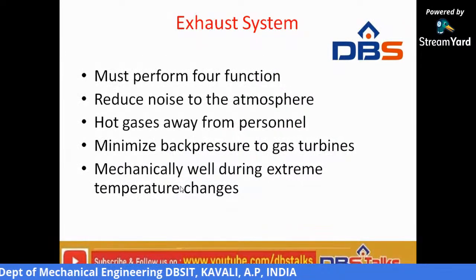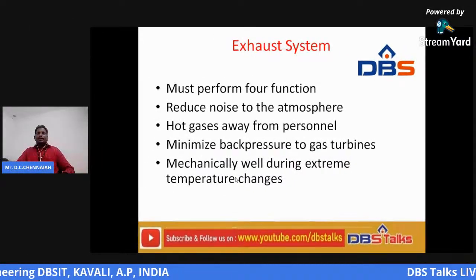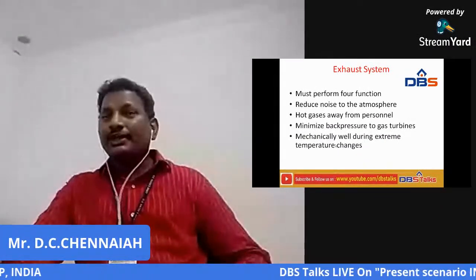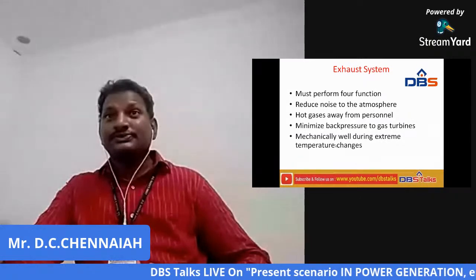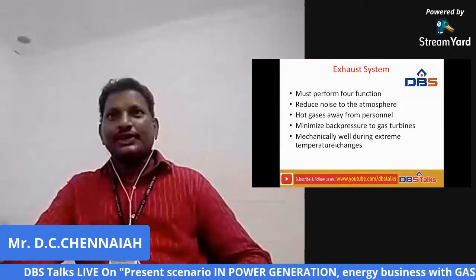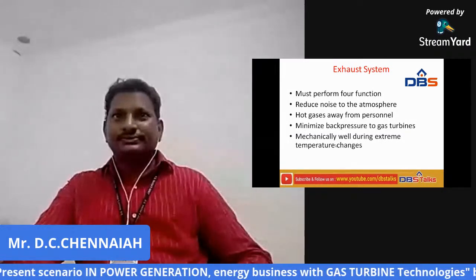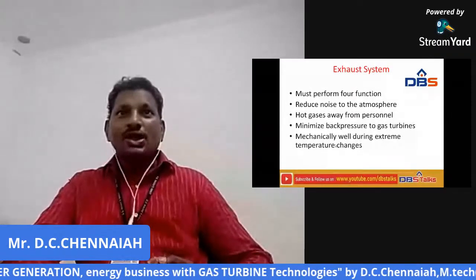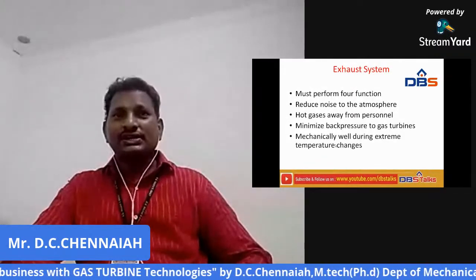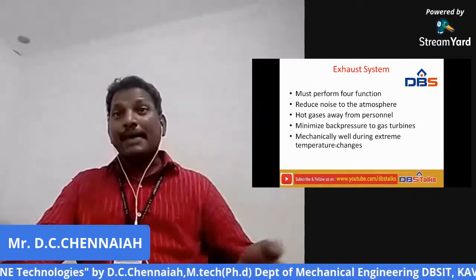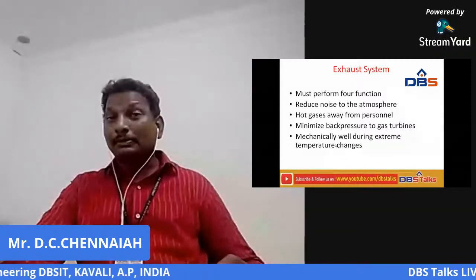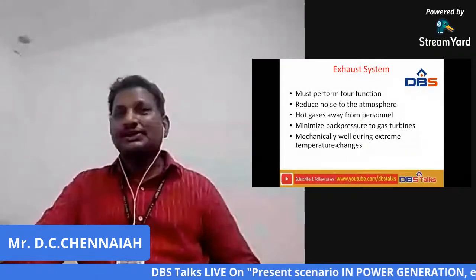Exhaust system. The exhaust system is a very important system which performs four functions. It must reduce noise to the atmosphere, carry hot gases away from personnel, and minimize the back pressure on the gas turbine. What is meant by back pressure? It is the pressure at which the gases are leaving the turbine.